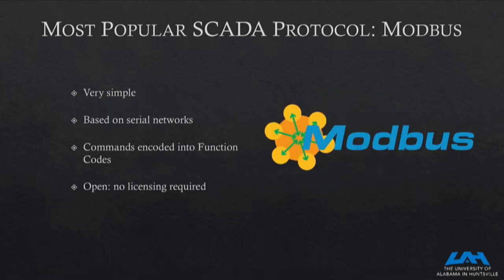The most popular SCADA protocol is Modbus. About 90% of PLCs support it, actually I haven't found any PLC that doesn't support Modbus. They usually support their own protocol plus something else plus Modbus. Everybody talks Modbus, and in essence Modbus is very simple, nothing very complicated about it. It's of course based on serial networks.